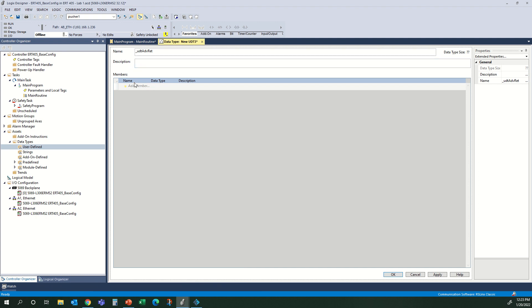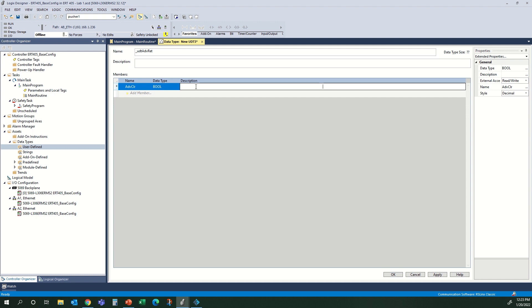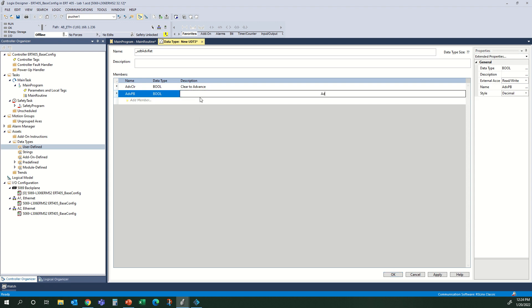So now we have a bunch of columns here. The first one is Name. My first element — or member — of the UDT is going to be the advance clear. This is a boolean. The description on this: the reason we're going to put descriptions on these is because they will automatically show up in your comments, which makes these very nice to use. We're going to call that 'Clear to Advance.' The next one is advance PB. You'll notice that I'm keeping these names fairly short and abbreviated so they don't take up a whole lot of room on your logic. To keep track of exactly what they are, that is what we have the description for.